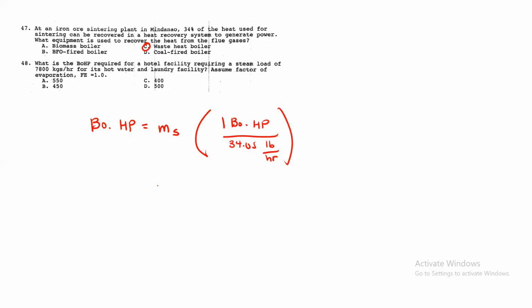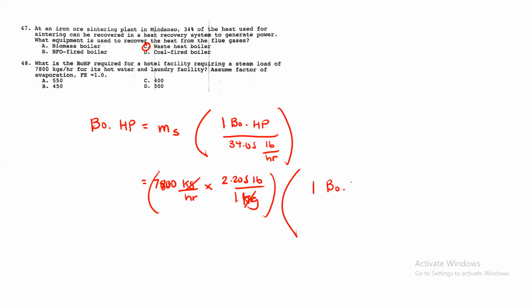So ilan yung mass ng steam natin? So mass ng steam, 7,800 kilograms per hour. So convert lang natin into pounds per hour. So times 2.205 pounds per 1 kilogram. Then multiplied by 1 boiler HP per 34.05 pounds per hour. So maka-cancel. Makuha natin sagot dito is 500 boiler HP.